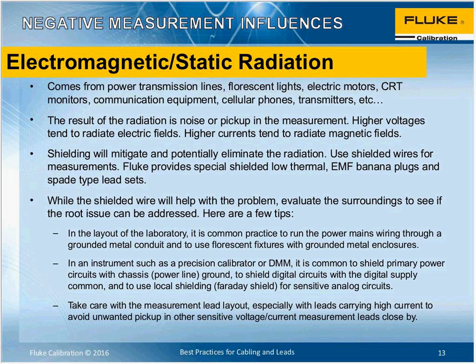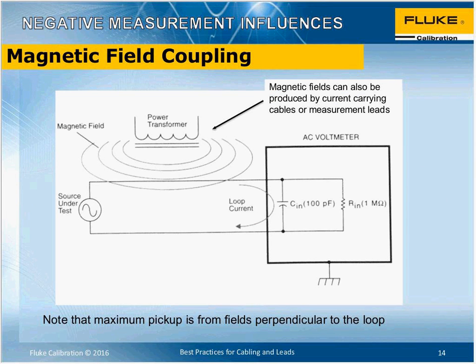And really this is what I've just been talking about in some kind of diagrammatic form. The issue here is that you get magnetic coupling loops. If you have a large loop in your measurement lead, that's much more susceptible to getting pickup than if it's a tight loop, because the magnetic field induces a voltage in the wire. Now, if those two wires are very, very close together, the voltage will be introduced into the high and into the low, which means that the differential, which your measuring instrument is sensing, is much less or even zero.